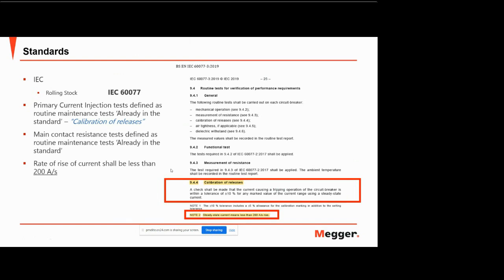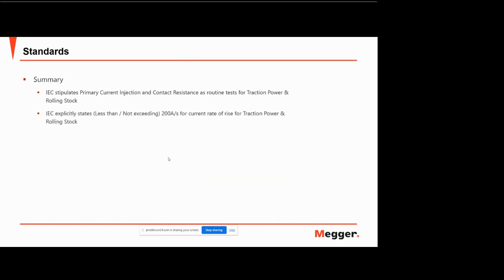So this applies to rolling stock, and as we've seen in the previous example, it applies to your traction power substation DC high-speed circuit breakers. It exists in both areas within the railway infrastructure, and it's defined as a routine test. So in summary, IEC stipulates that the primary current injection and the contact resistance for traction power and rolling stock are defined as routine tests. It also explicitly states that the current shall not exceed 200 amps per second for the rate of rise. That is to make sure that we don't increase the current too quickly, because if you do, you potentially miss the point at which the breaker trips, because you're injecting the current at a rate at which it cannot react quickly enough to turn the current off.